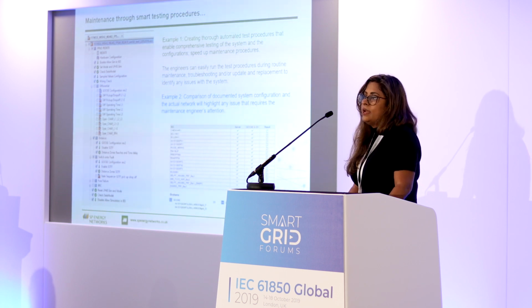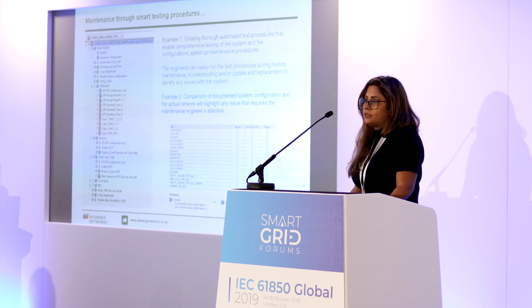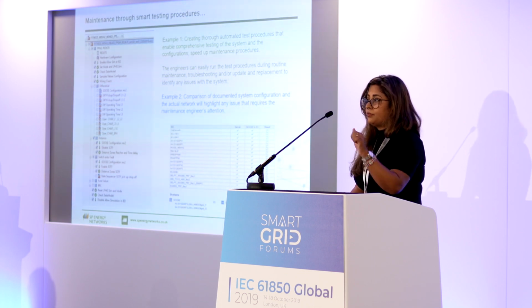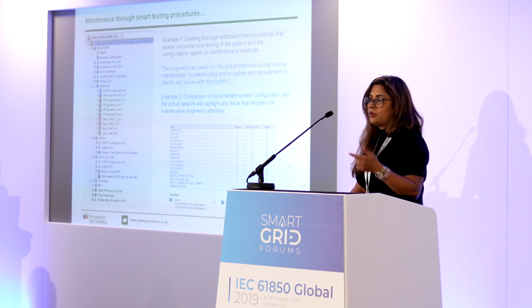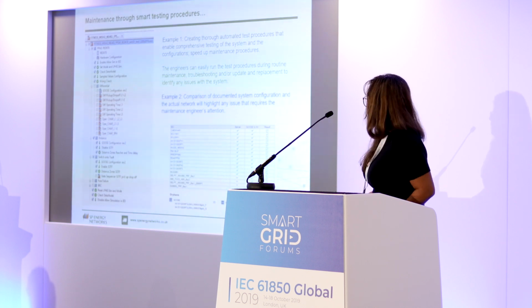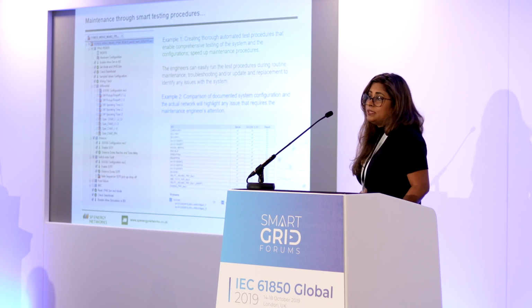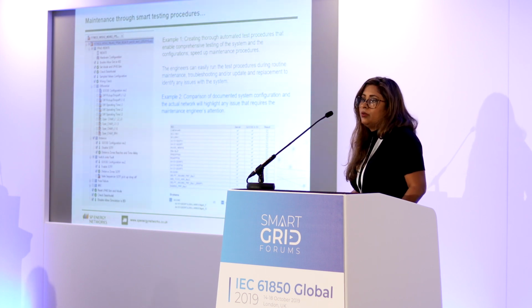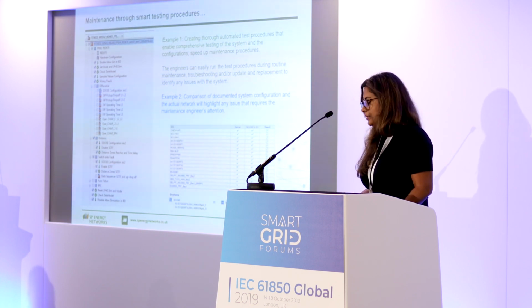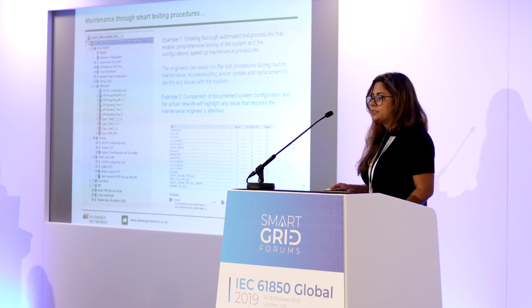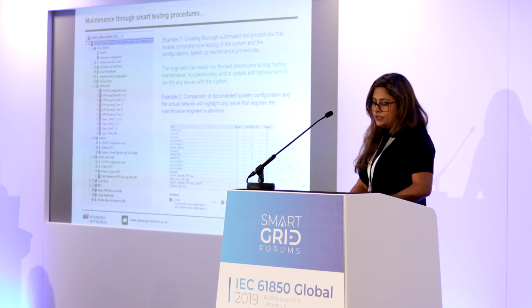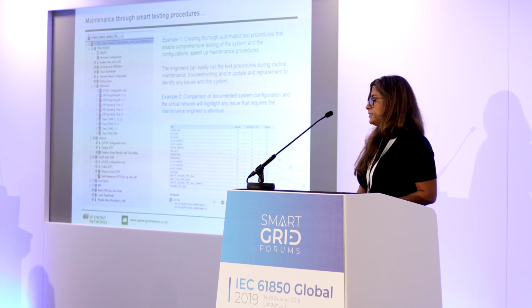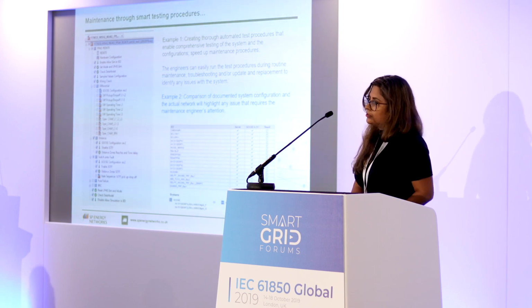There are tools in the market that let you do this. You take your last SCD file, the one documented and signed off after commissioning, and compare it to what's happening on the network. If anything is off, you'll see it, and that gives you your first clue as to what's going wrong, especially if there's no other obvious indication of failure. These are just two examples; there are many more smart testing procedures you can deploy to make your maintenance regime easier.